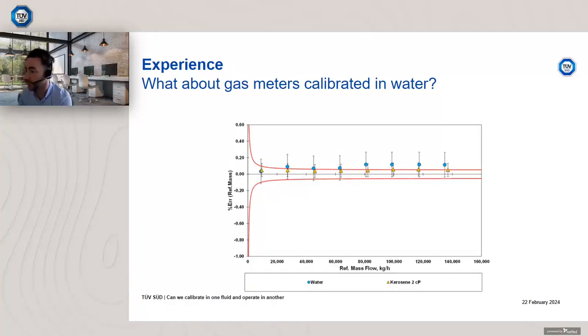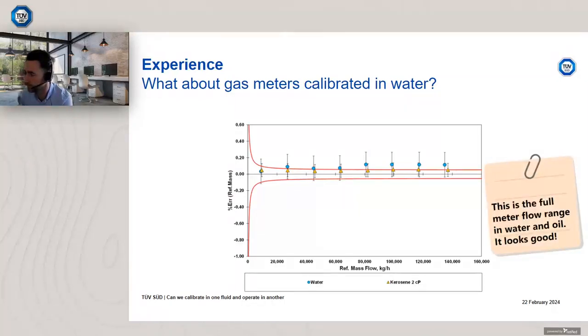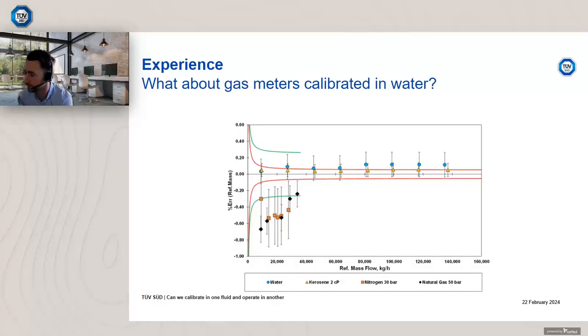You can see that both sets of data look okay. The kerosene slightly better than the water. However, please bear in mind this water facility actually has a higher uncertainty than kerosene. Both results are pretty close to the specification, certainly when you factor in the uncertainty bars. But what about gas? I've now included some data for this device that was kindly supplied to me for nitrogen and natural gas.